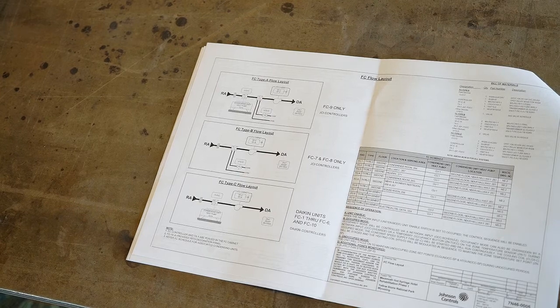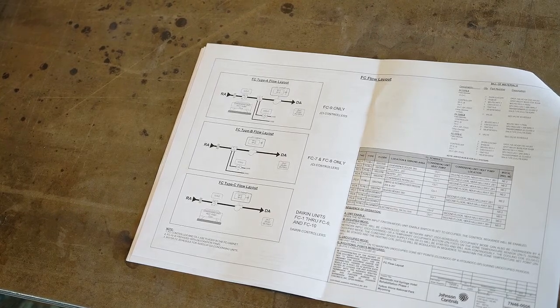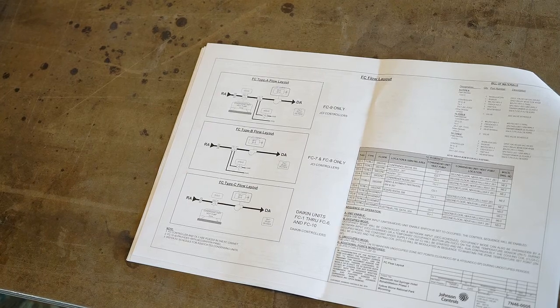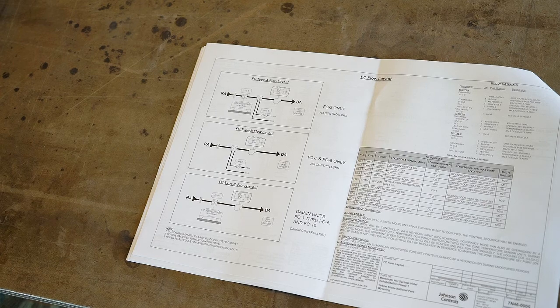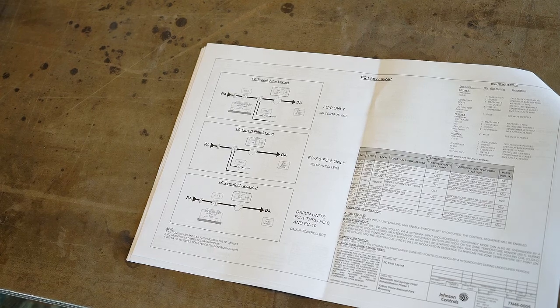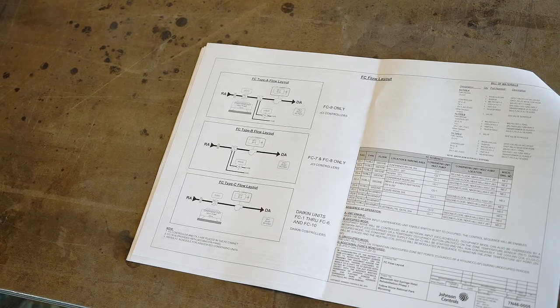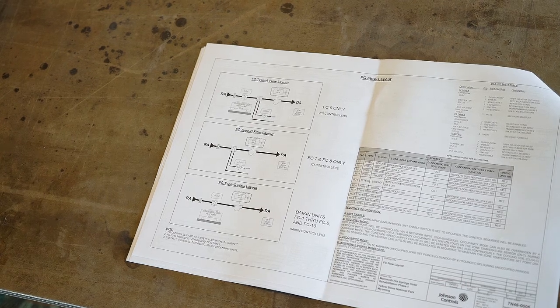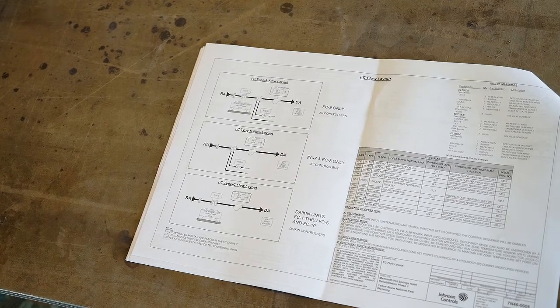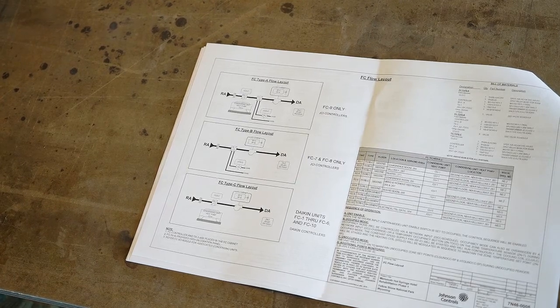So to control when it's on, what we do is give it an enable to turn it on, based on your thermostat. There's a thermostat in the gift shop? That is correct. So if it's set to auto and you set it to a temperature, it'll decide whether to run the DX or run the hydronic heating? That is correct. Yep. Oh, then it's run by the temperature controller. It is.